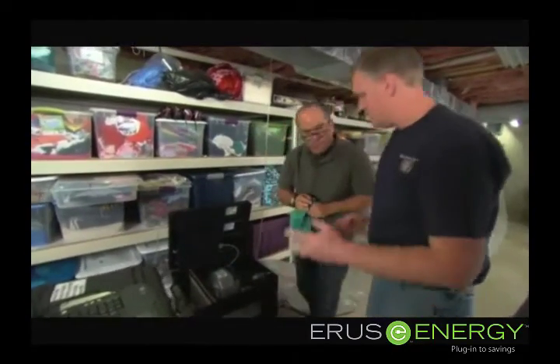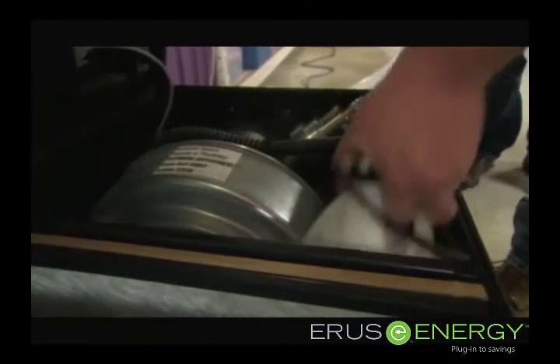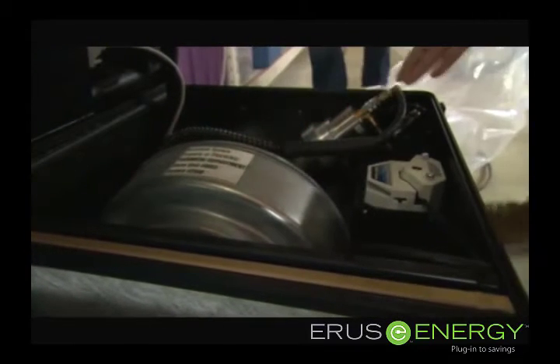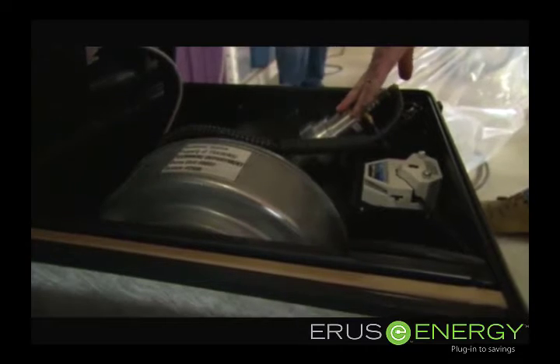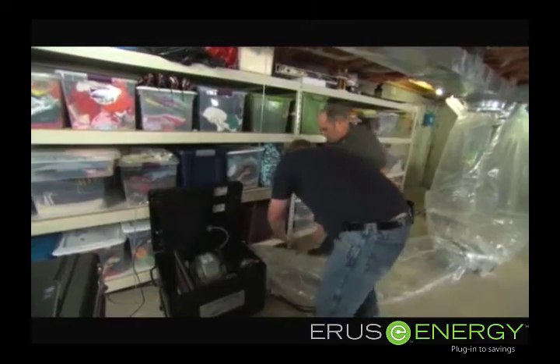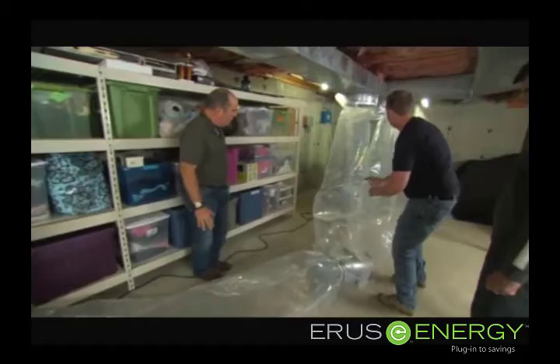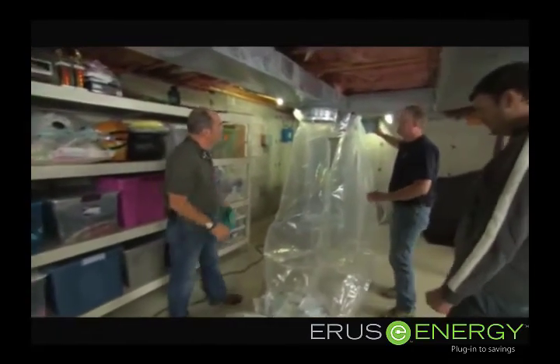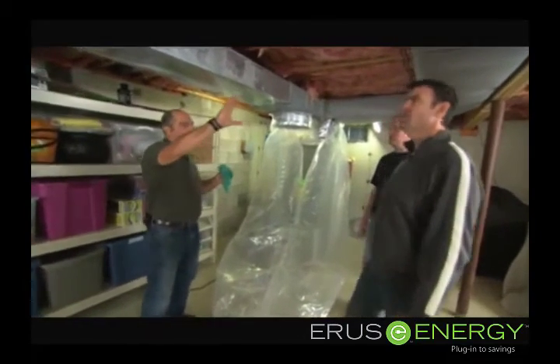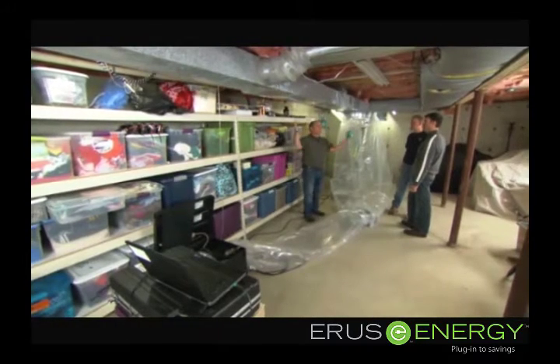So in order to seal the ducts, we need to do it as an aerosol. So we're going to use this sealant. We use the same fan that we used for the pre-test. We have a nozzle that injects the liquid into the duct. The small particles that are now in aerosol travel through this flexible duct here to a Y branch. Gotcha. Then it can go to the return and the supply, and we seal both at the same time. You've got heated air coming out here. We want to keep that in the ductwork. Well, on the return side, it's under a negative pressure, so it's pulling air in.